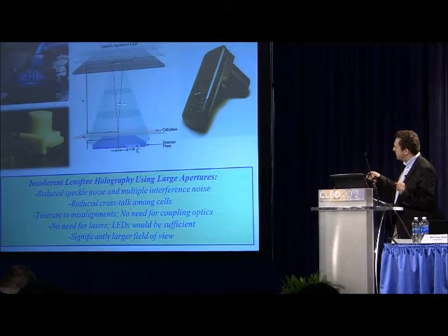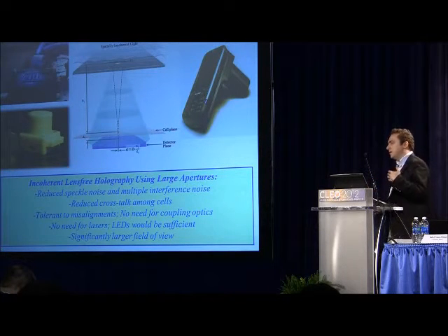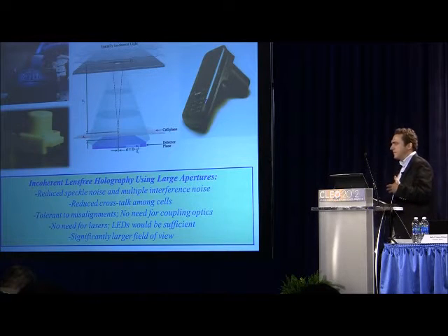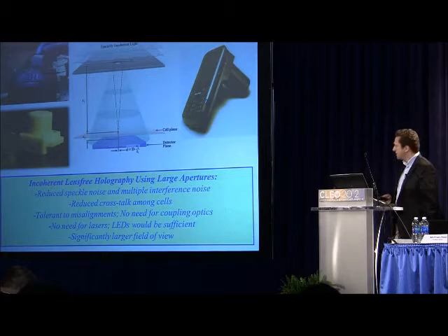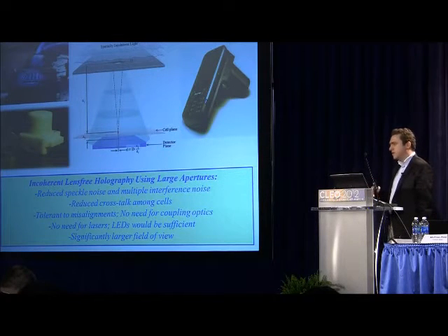And we can do this over a very large field of view under unit magnification, directly scaling up with the active area of the sensor. For instance, this microscope has an active area of 24 square millimeters, which means you can do microscopy with 1 to 2 micron resolution across that large field of view, which is quite important.